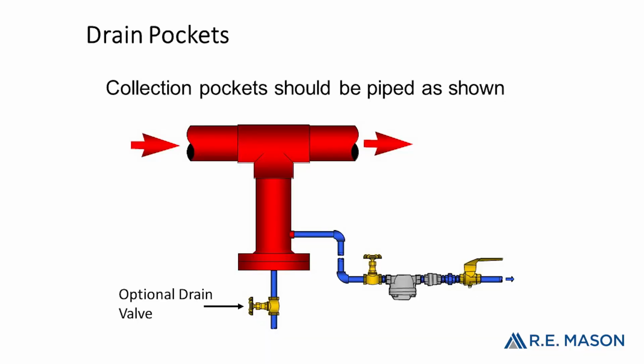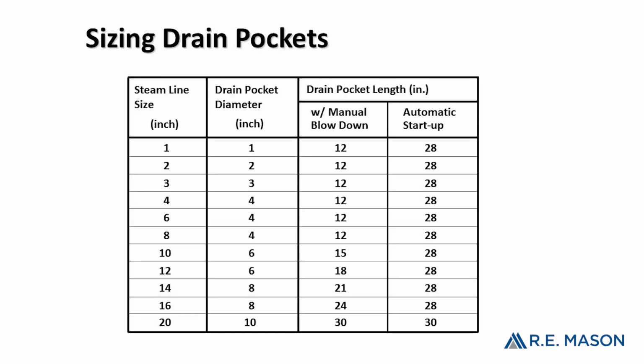The other thing is your drip pockets. This is one of the biggest areas. Your drip pocket, depending on the size of your pipe, is designed to be a certain size. So often we come in, you have like 10-inch pipe with a 3/4 inch drip coming off the bottom of it. And the last time I checked, there was not a stop sign in the pipe saying condensate stop, fall in here. And at 80 miles an hour, it's just going to go over. We're not going to remove it. The trap will be working, but we're not removing condensate. Just an example of what those pockets should be.